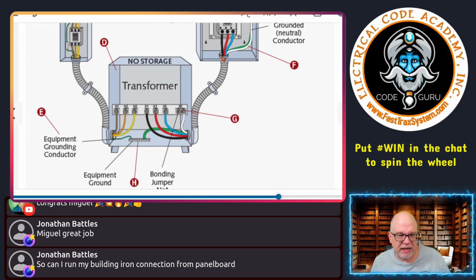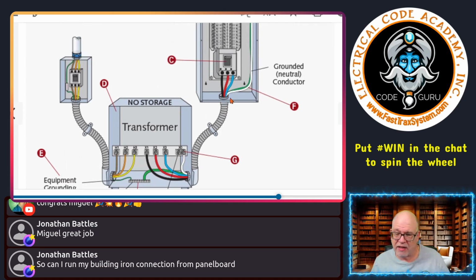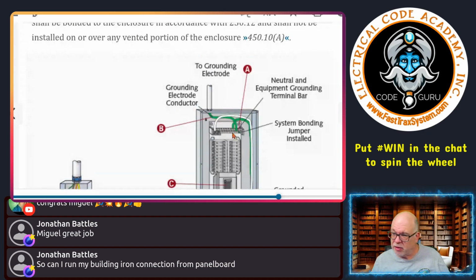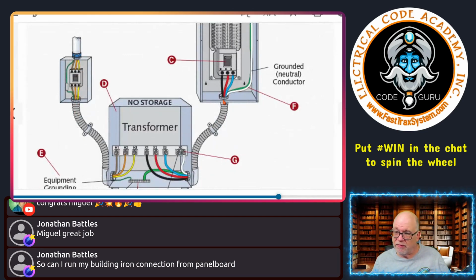Now, you could run into something on this end which may be impaired, concentric, eccentric, something like that. The best advice here is remove it and just treat it as non-impairment. And if that's the scenario, you only have to get into advanced bonding requirements if it is dealing with over 250 volts to ground. Now, chances are this one's not. This would probably be like a 208/120 or a 240/120 because of the color scheming, although this is not a requirement of the code. But typically, in looking at this, this is probably going to be feeding a 120/208 panel.